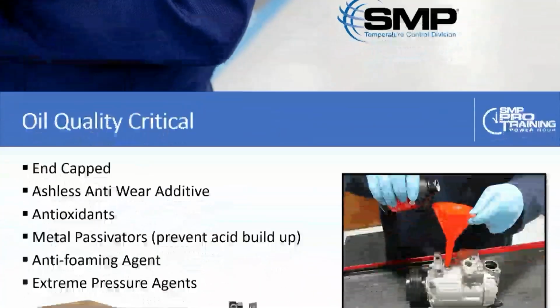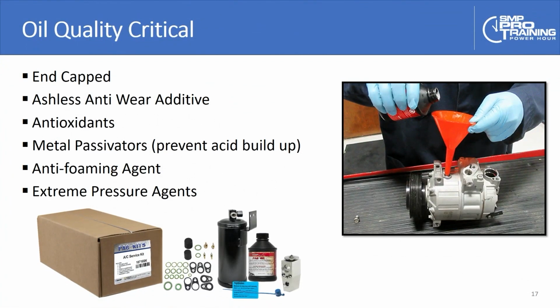So I just wanted to be sure that we understood the lubrication situation there. If I'm adding oil to or draining oil from this compressor, I need to do it through the drain plug. I mentioned this in our session last month. I cannot overemphasize the importance of choosing a quality oil. Good oils have a myriad of properties: they're end-capped, and have antioxidants, metal passivators, and anti-foaming agents. There's a lot of science that goes into the development of oils. So when you're adding oil to one of these compressors, it's important that you choose the right oil.